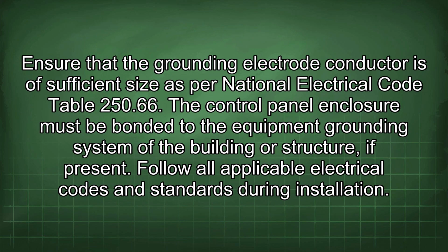Ensure that the grounding electrode conductor is of sufficient size as per National Electrical Code Table 250.66. The control panel enclosure must be bonded to the equipment grounding system of the building or structure, if present. Follow all applicable electrical codes and standards during installation.